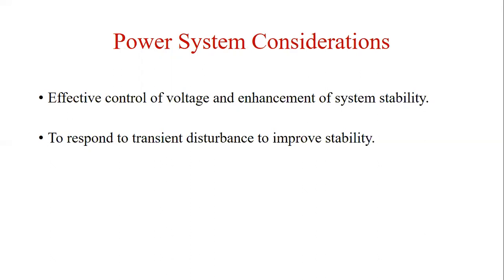From the power system point of view, the excitation system should contribute to effective control of voltage and enhancement of power system stability. It should be capable of responding rapidly to disturbances so as to enhance transient stability, and of modulating the generator field so as to enhance small signal stability of the power system. Historically, the role of the excitation system in enhancing power system performance has been growing continuously.